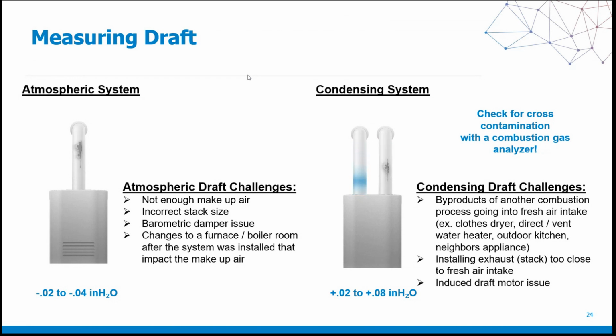Do we have cracks in the seams of the PVC piping that we've been using up to this point? Because I know you're all going to use polypropylene now after I just went over it. But if we have cracks in the connections or in the seams of our PVC piping, that is preventing the flue gases from exiting properly. That's an issue. And anytime flue gases do not exit a system properly, those flue gases go down into the combustion zone, whether it's atmospheric or condensing. And when they do, they start to wear away and eat away at the combustion zone itself, because those byproducts of combustion are not meant to be backdrafted down in.